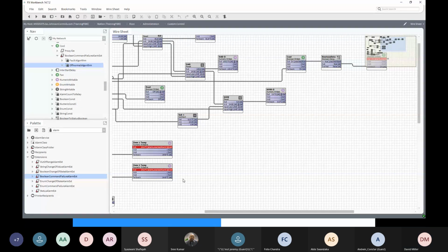The only time you might would be if you had to do something in the field, like turn a light on the switchboard or in the corridor or something like that, to indicate that you've got an alarm condition. But other than that, if the alarm is really just intended to be put in front of an operator in an alarm console or send us an email, then I would do it this way in the supervisor.